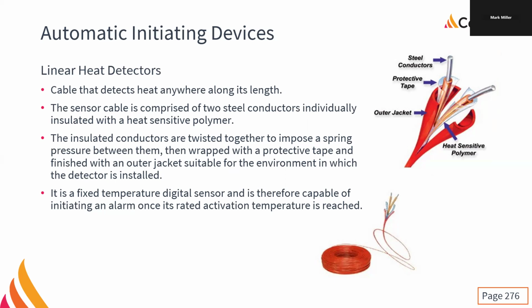We use it to protect very large, complicated areas, because we can mount it directly to racking in a warehouse. So we can protect each bay where you would put skids. I've used it mostly in aircraft hangars as additional detection, tie wrapped to the sprinkler lines, and also in warehousing, especially cold storage warehousing. The entire building's like 15 below zero. You can't use smoke detectors; way too cold. Linear heat detection is a great option.